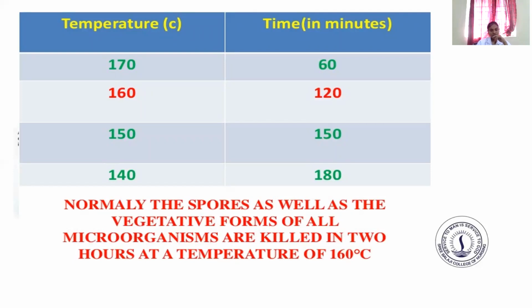And then we have to maintain some temperature and timing. At 170 degrees centigrade, we maintain 60 minutes. At 160 degrees centigrade, we maintain 120 minutes. At 150 degrees centigrade, we maintain 150 minutes. At 140 degrees centigrade, we maintain 180 minutes. Normally, the spores as well as the vegetative forms of all microorganisms are killed in 2 hours at a temperature of 160 degrees centigrade.